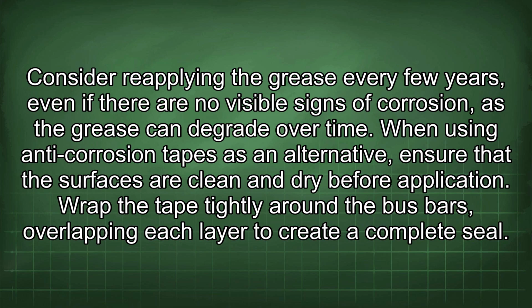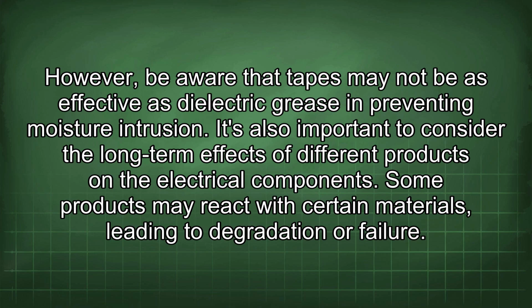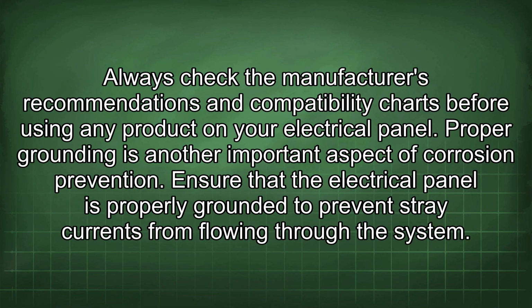Wrap the tape tightly around the bus bars, overlapping each layer to create a complete seal. However, be aware that tapes may not be as effective as dielectric grease in preventing moisture intrusion. It's also important to consider the long-term effects of different products on the electrical components. Some products may react with certain materials, leading to degradation or failure. Always check the manufacturer's recommendations and compatibility charts before using any product on your electrical panel.